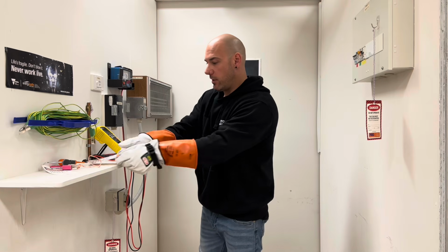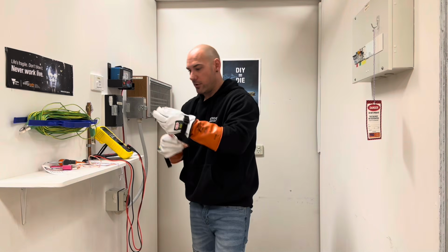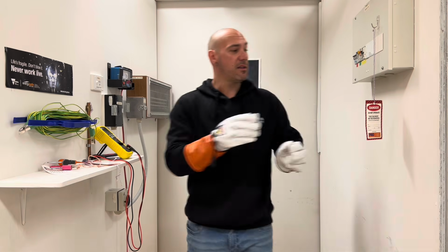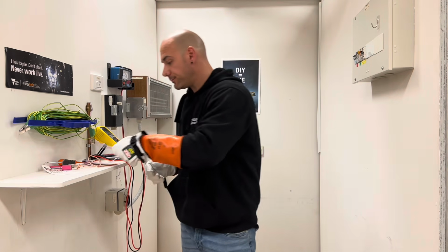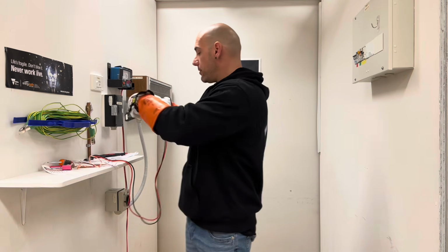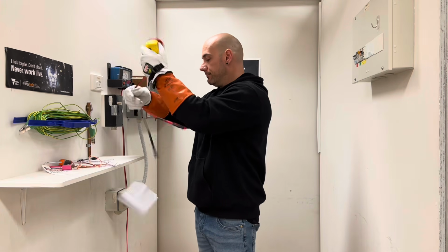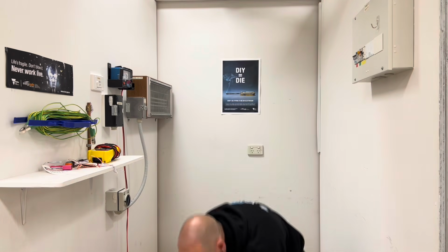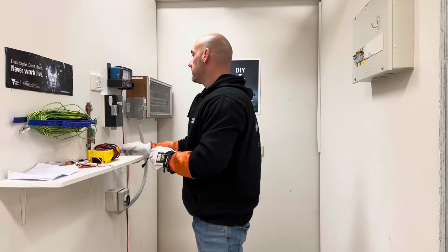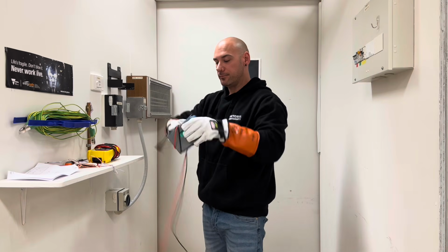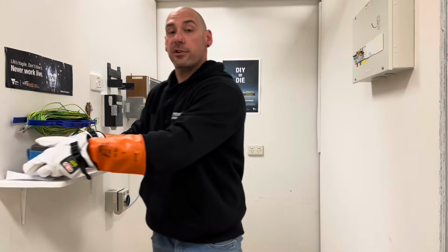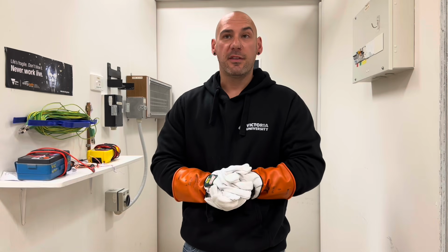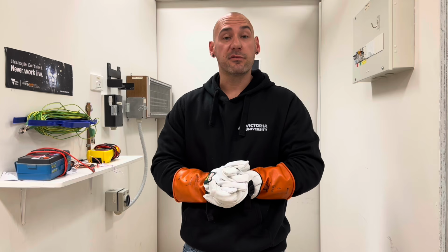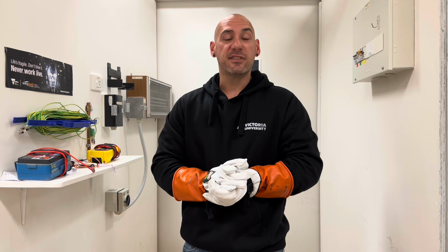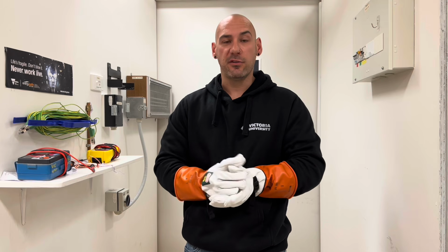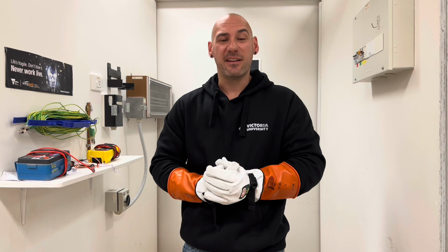One from the heater, one on the isolator, and the one at the switchboard. Clean your work area up. And at this point you will speak to the customer and let them know that you will issue them a certificate of electrical safety. If the job was disconnected and reconnected on separate days, you would have to do a risk assessment for each day and a certificate for each day.